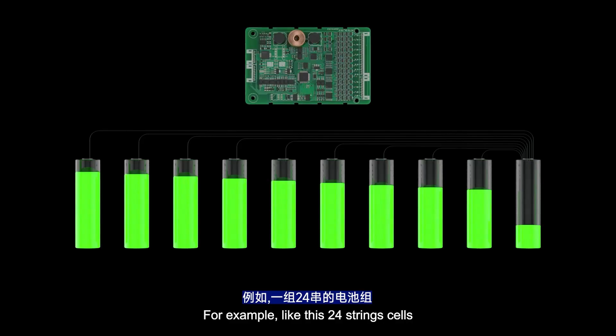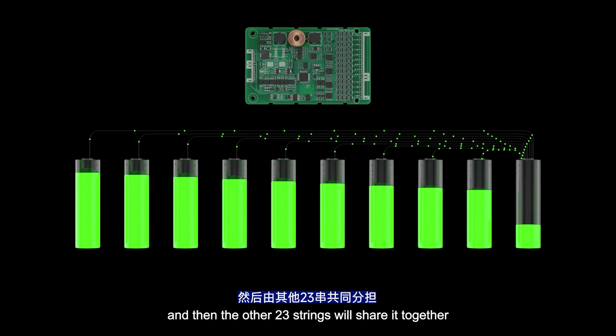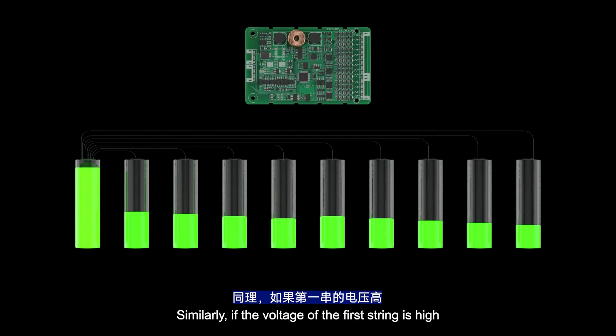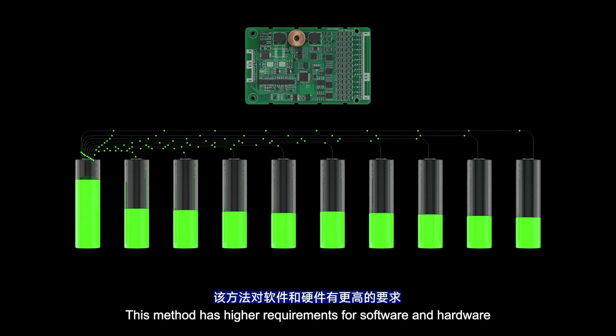Different from the above two, transformer type equalization adopts an overall solution. For example, with 24 strings of cells, if the voltage of the last string is low, the chip will calculate the amount of voltage to be added. Then the other 23 strings will share it together, each providing 1/23 of the needed voltage for that string. Similarly, if the voltage of the first string is high, the chip will divide the voltage that needs to be reduced into 23 parts and distribute it to each string of cells. This method has higher requirements for software and hardware, and the equalization effect is also better.